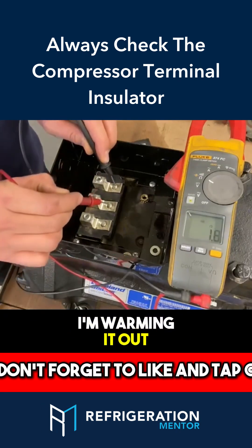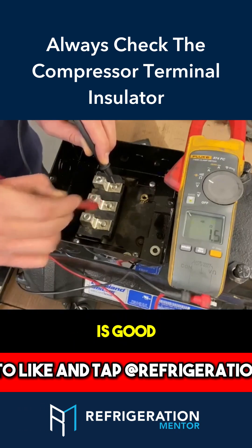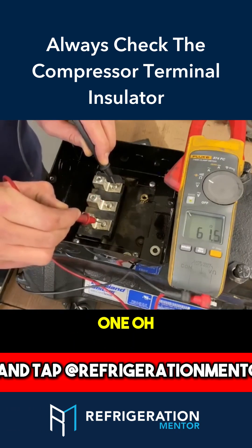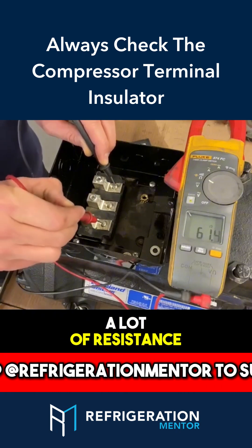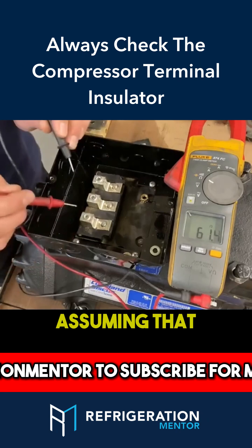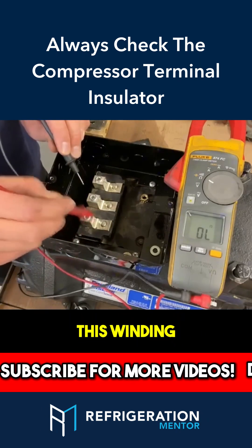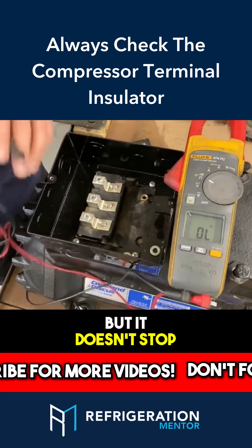I'll do a quick one — ohming it out now. So 1.5 ohms; we know this winding is good. We go to this one — well, this one we got a lot of resistance here, and then we got more here. So right now we're assuming that this is a failed winding or something's wrong with it, but it doesn't stop there.